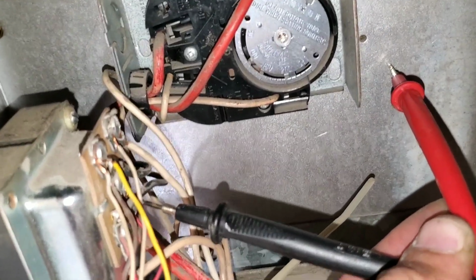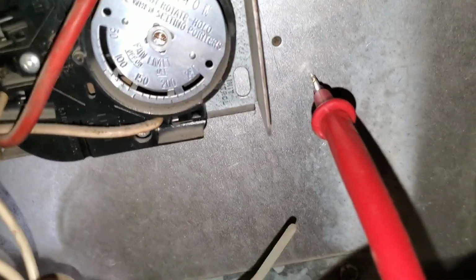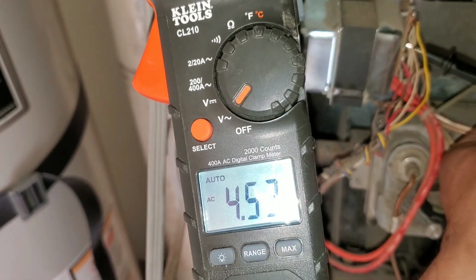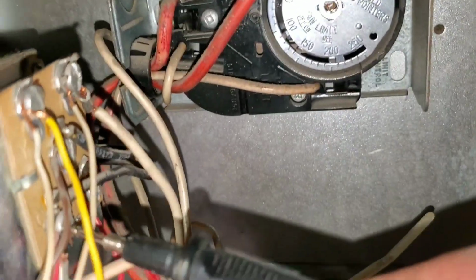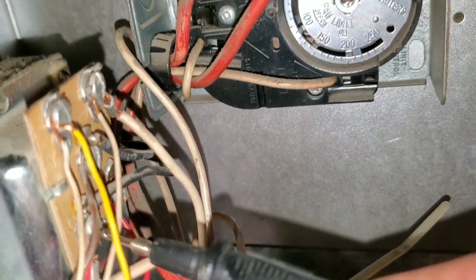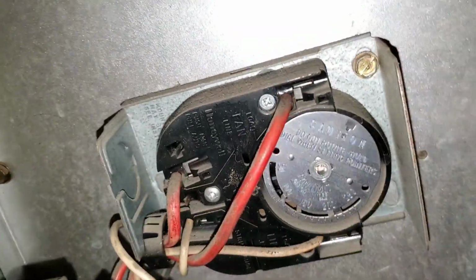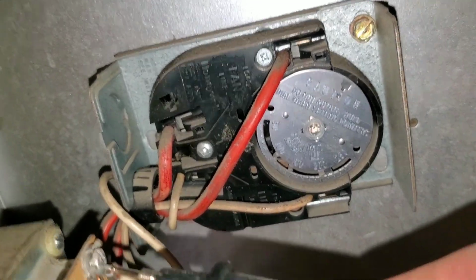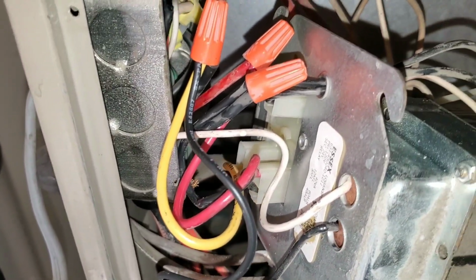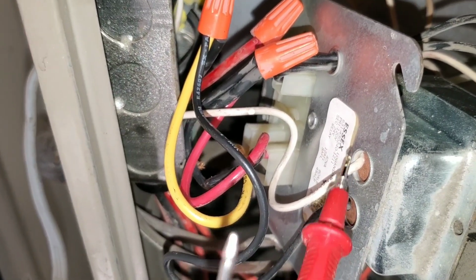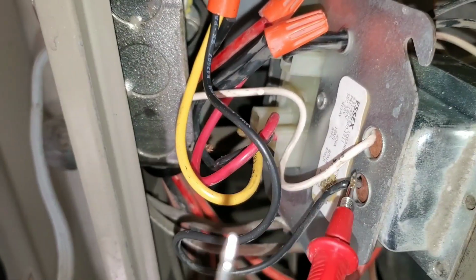Here I'm at the transformer. I have one of my leads to ground. I have one of my leads here to the transformer on the R terminal. And you can see I'm not getting the proper voltage. Here I'm checking my C terminal. This will be my Y terminal, and I'm not getting voltage. What you want to do is check the 120 volts that supply your transformer.